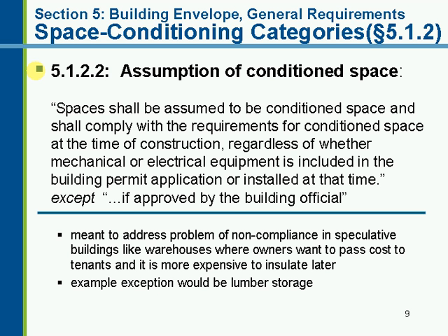And for example, in our city, it's fairly common for large buildings that the shell will be constructed first and then mechanical and electrical will come later. But the insulation, all that needs to be done at the time of the construction of the shell. Now, there is an exception here if approved by the building official. There are atypical cases, but some cases, such as lumber storage, where it's really unlikely that the building would not be heated or cooled later on. But we do not give this exemption for warehouse type of spaces.